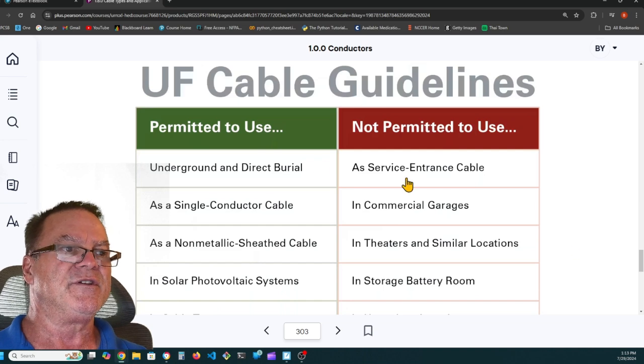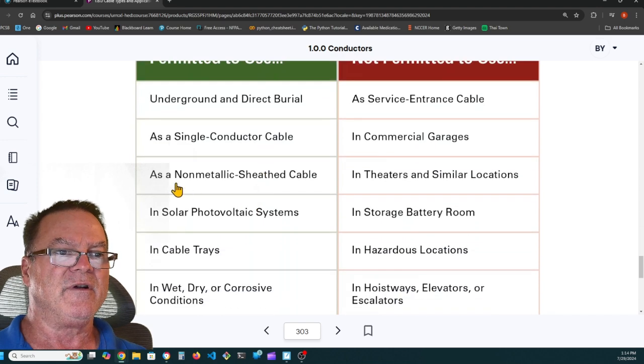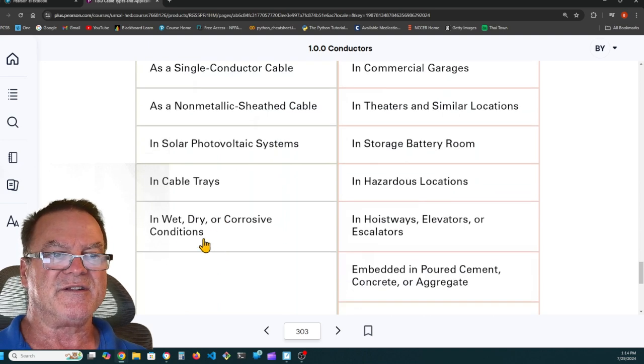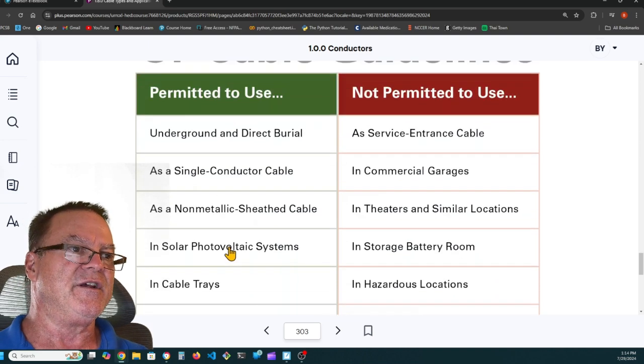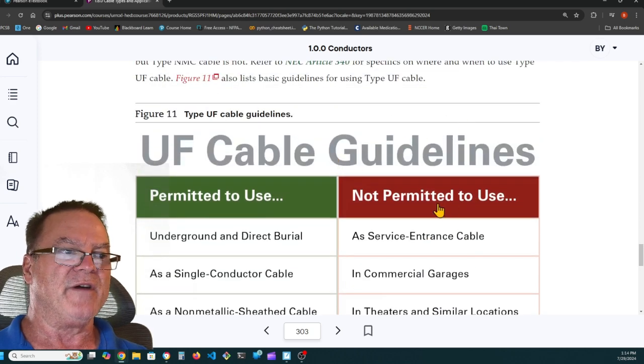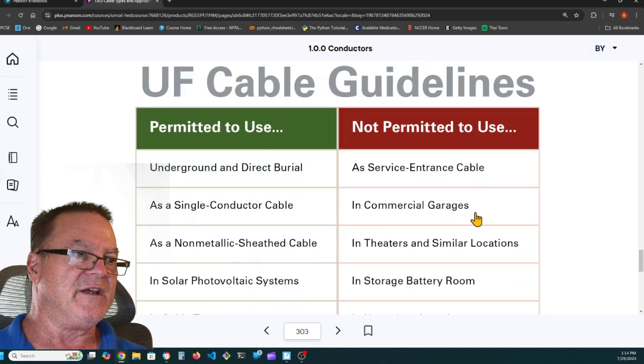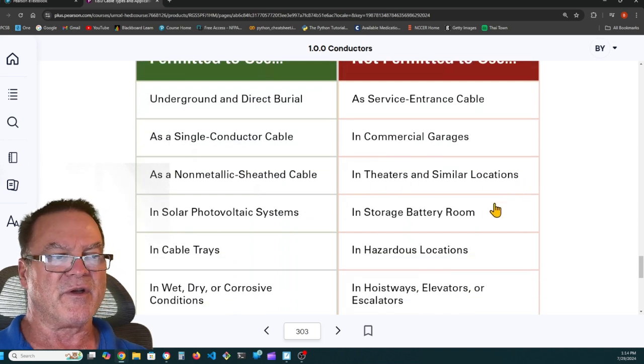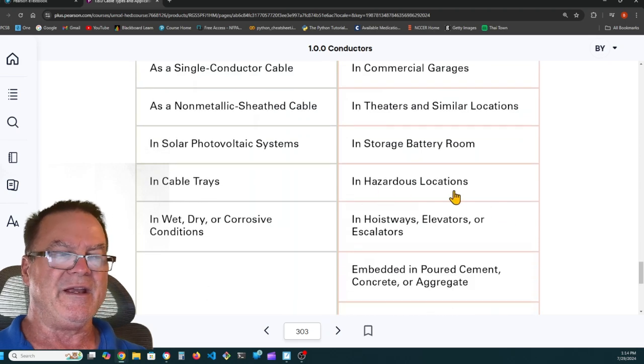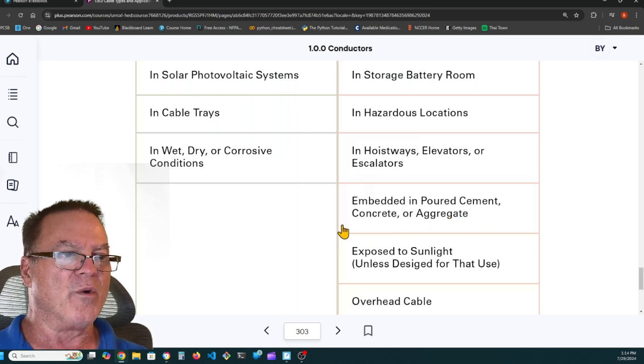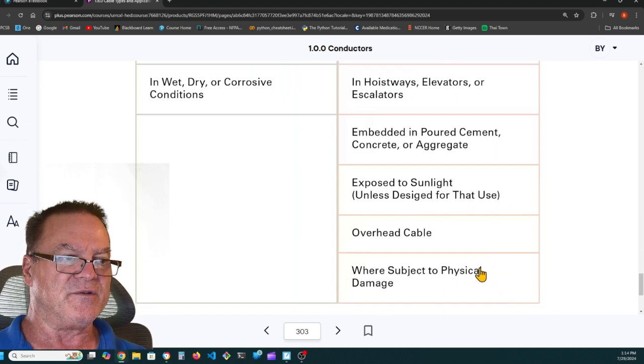So you're allowed to use UF cable underground and direct buried, as a single conductor cable, as non-metallic sheathed cable, in solar photovoltaic systems, in cable trays, in wet, dry, or corrosive conditions. You're not allowed to use UF cable as service entrance cable, in commercial garages, in theaters and similar locations, in storage battery rooms, in hazardous locations, in hoistways, elevators, or escalators, embedded in poured concrete, cement, or aggregate, exposed to sunlight unless designed for that use, as overhead cables, and where subject to physical damage.